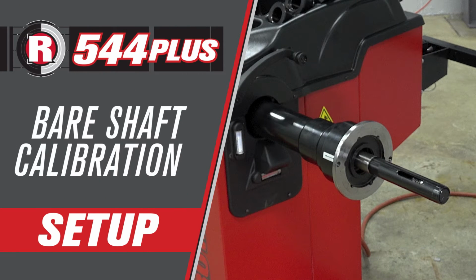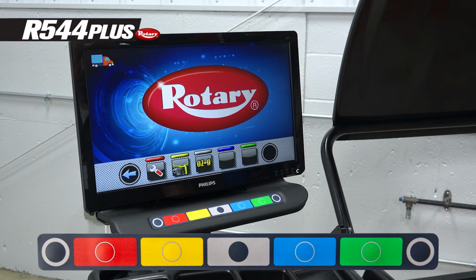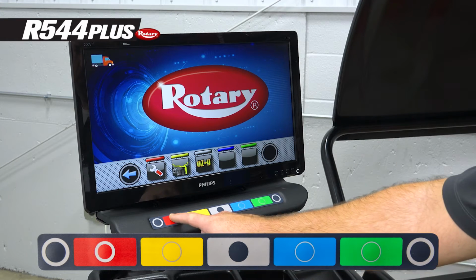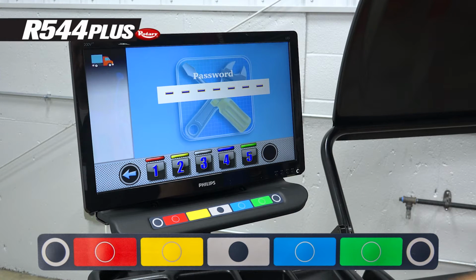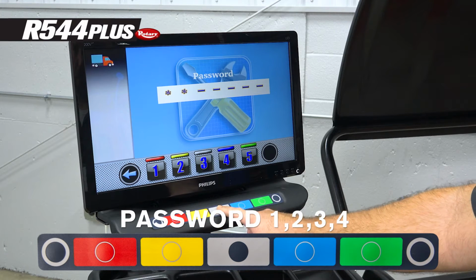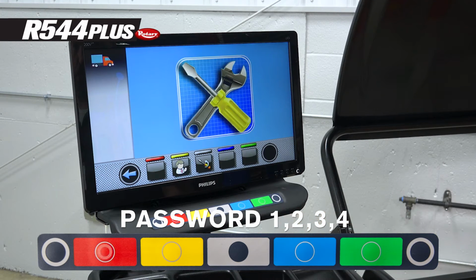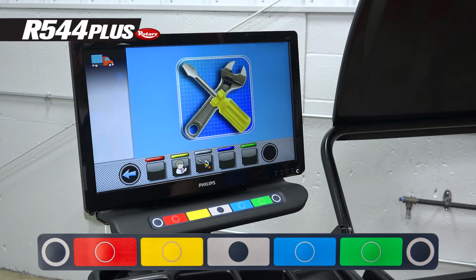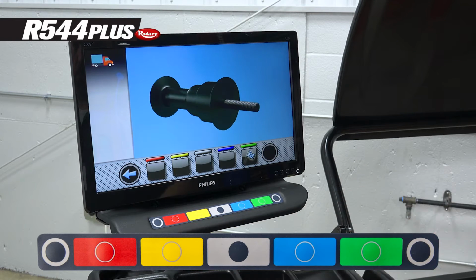Bare shaft calibration. To do the bare shaft calibration, press the red button for the wrench icon. Enter the password 1234 by pressing the red, yellow, gray, then blue button. Now press the gray button for the screwdriver icon. Then press the red button for the bare shaft calibration.